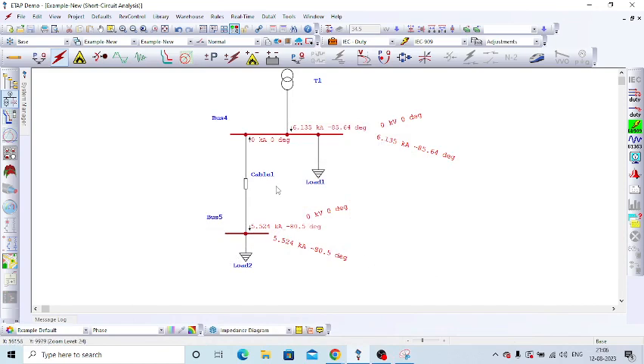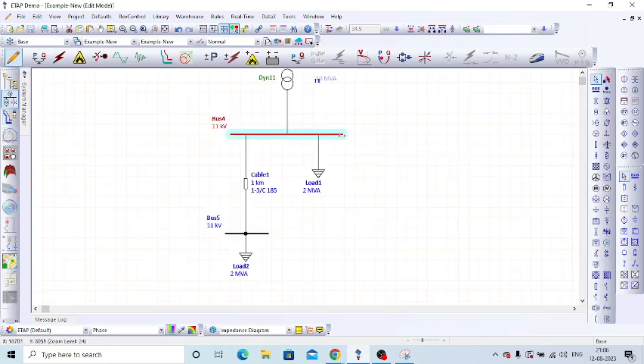So the impedance offered by the cable will limit some fault current. Because of that, the fault current magnitude at this bus location is lesser compared to this bus. I will now introduce one more case. I'm just going to copy paste the same cable. All the properties of this cable and this cable remain the same. Can you see the difference? Here it is cable 1, but when I copy and paste it, it becomes cable 3.